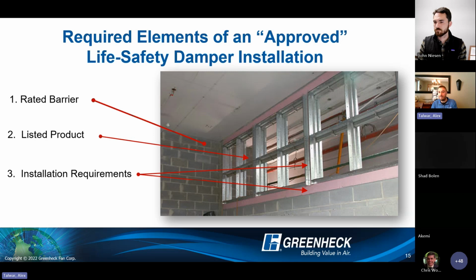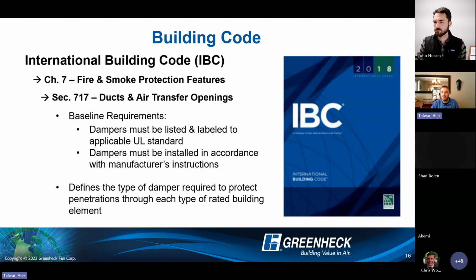So, you pick the right product for the right barrier. It's a UL product, but someone installs it however they want. We don't know if that installation method is approved unless we are sure that they are following a manufacturer's installation method or approved alternative. So there are other possibilities as well for installing these products, but it does need to be a UL approved document that has been adhered to.